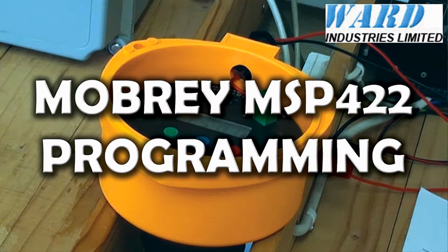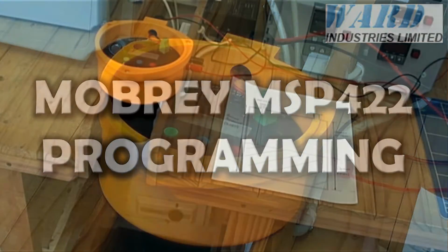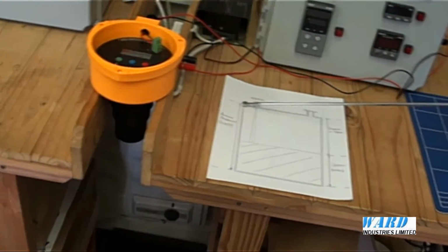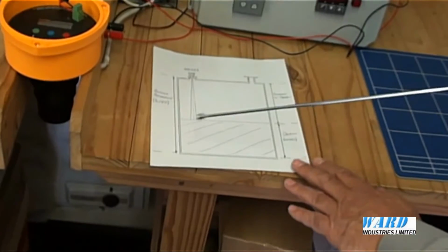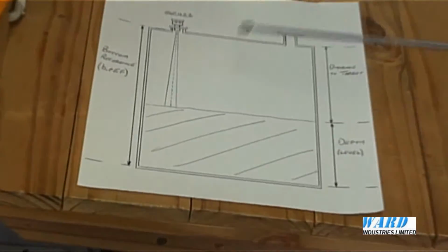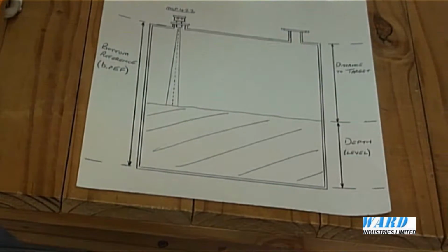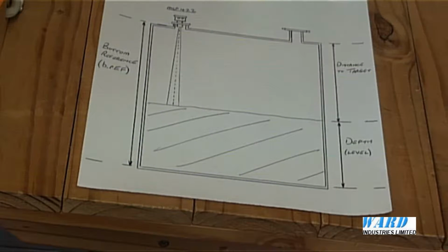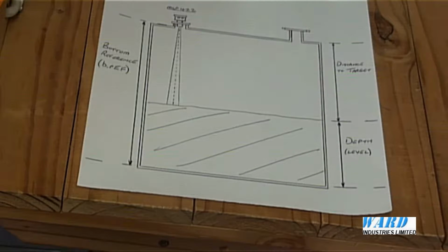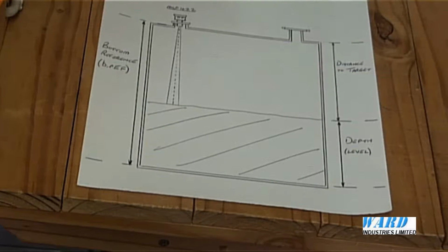Let's look at how we can set the parameter values. The first value we want to set is the bottom reference value, Bref. This is the distance from the transmitter face to the bottom of the tank. With this particular model, MSP422-B28, the factory default value is 8 meters.